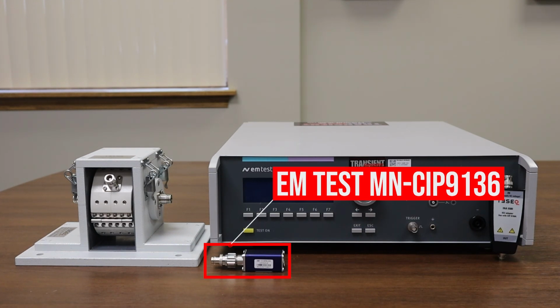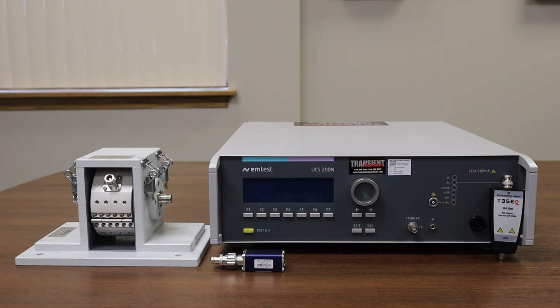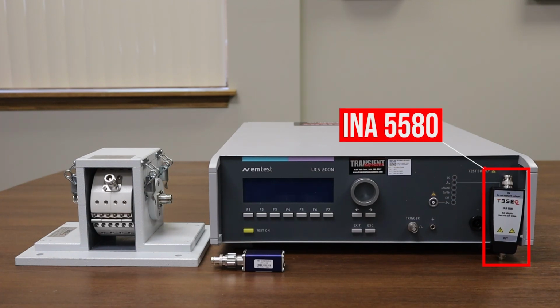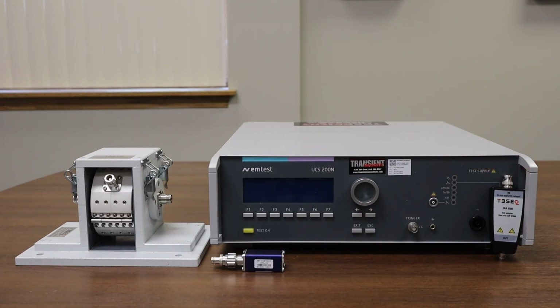MN-CIP 9136. The MN-CIP 9136 impedance matching adapter is designed for use with the EMTest UCS 200N series of automotive transient generators. For the Teseq NSG 5500 series, the INA 5580 is used, which you can see in the front on the right side of our UCS 200N. These impedance matching networks are used during the level setting and are adjusted individually for a particular BCI probe.